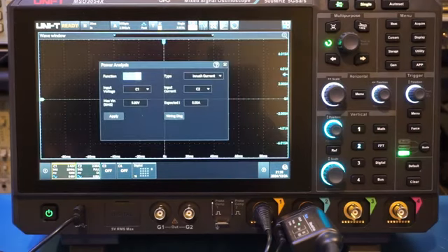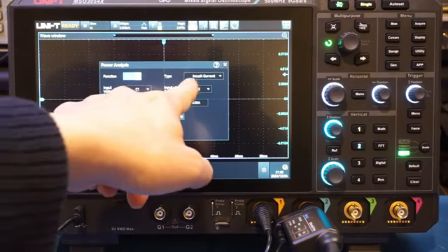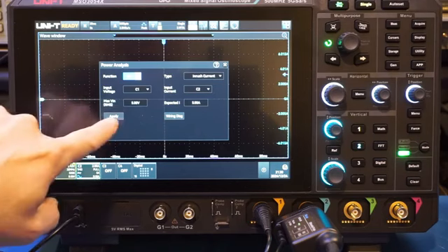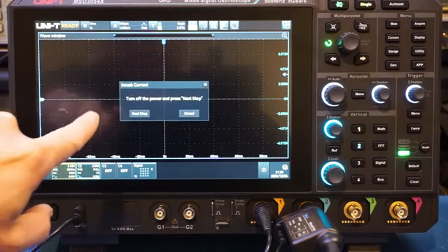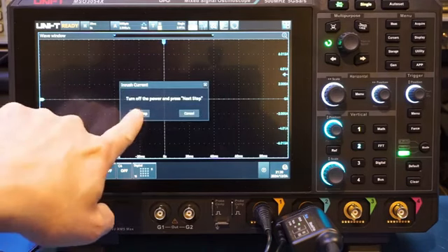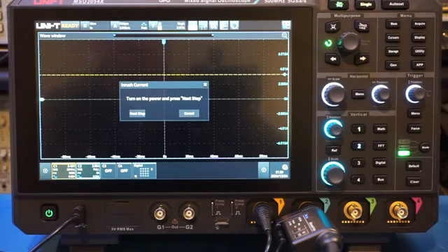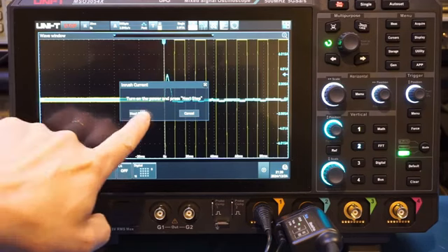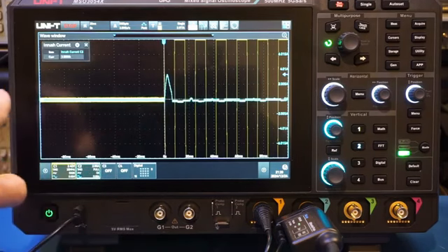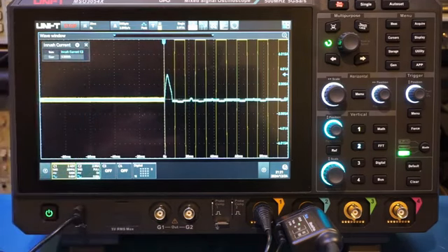Now let's briefly take a look at the inrush current. For the inrush current measurement, I have turned the type to inrush current. And let's apply. Turn off the power supply. Yes, it's off. Next step. Turn on the power supply. Okay. And press next step. And you can see that we have measured inrush current here. It is at 3.3 amps.